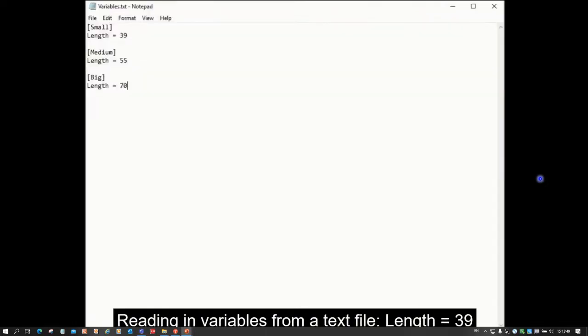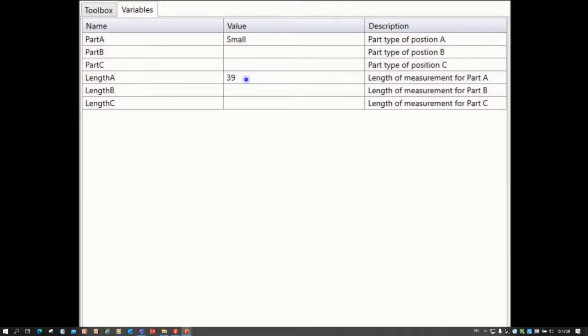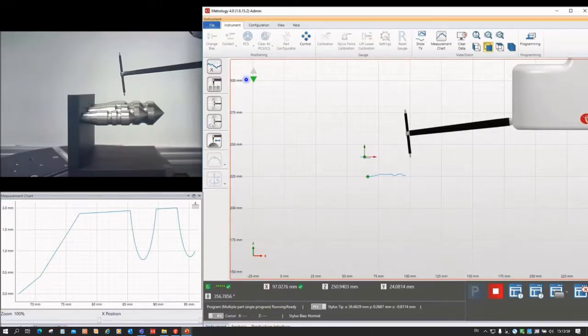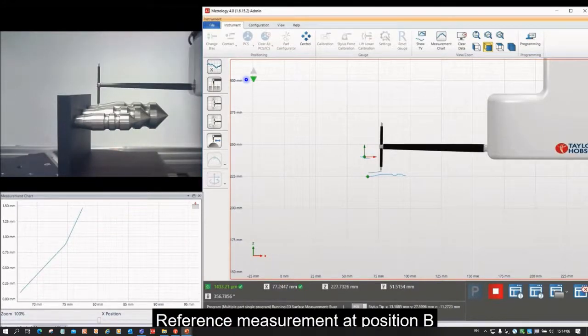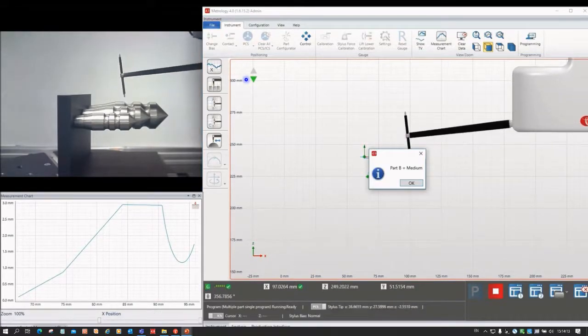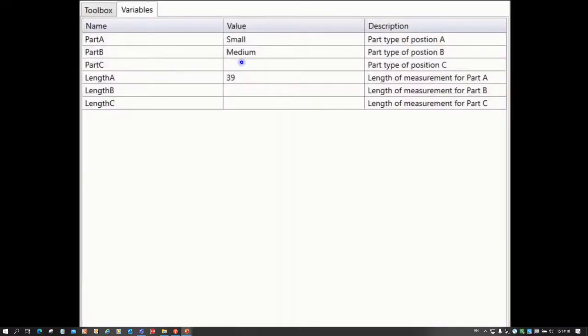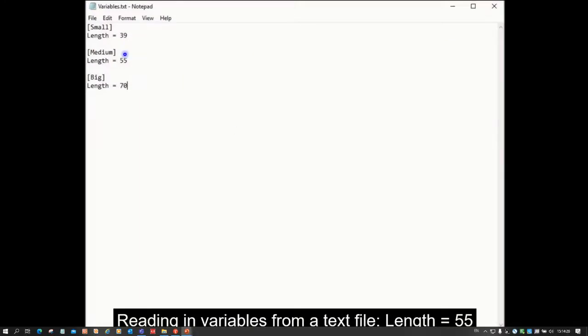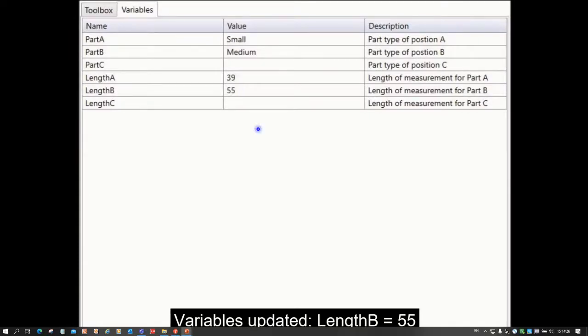And so Part A has been identified, and it reads in the length of 39 millimeters there for the small part and it fits that back into the table. This is all happening in the background, and this is just to illustrate how this is working. Now it's going to do the same thing on the middle part and say what is this part. And this time it's identified that it's a medium-sized part. And it's identified the medium-sized part, it then goes and looks up in the database or in the text file there, and it says this medium-sized part is 55 millimeters long.